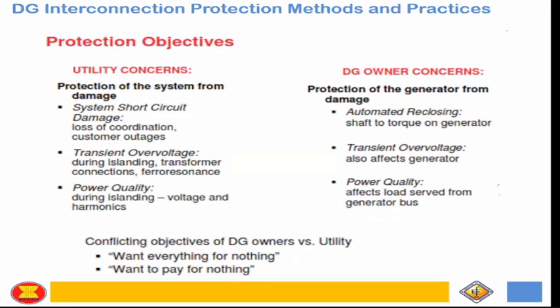Explain in layman's terms the requirement for the DG side, and also for the utility. On the utility side, we should also know and see the potential risk of distributed generation or its impact, or else the appliances of our consumers might be damaged. Okay? So who will be held accountable? Not the DG. We are the owner of the system; we are in charge. We are to protect the distribution system, so we ensure its impact. That is what we need to identify. And in the worst case, our equipment might be damaged, and our high voltage side equipment is very expensive.